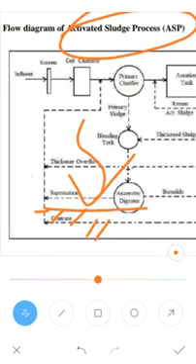In the activated sludge process, the organic matter and biological flocs are suspended in a liquid medium containing dissolved oxygen. Aeration conditions must be attained in the tanks. However, in the clarifier the dissolved oxygen concentration can become extremely low. Dissolved oxygen extracted from the mixed liquor is replenished by the supply to the aeration tanks.